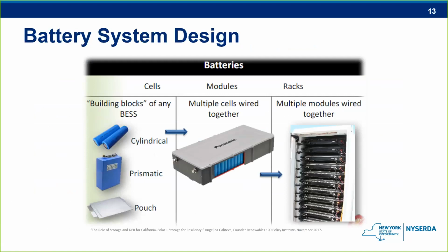All right, so every energy storage system is usually going to consist of at least these three components. The first, over on the left-hand side, is the cell that's considered the building block of the system. They tend to be smaller. They might range in size from something akin to a AA battery or what's in your cell phone to perhaps maybe even the size of a small tablet. Next component is the module, which just really consists of multiple cells that are wired together. And then when multiple modules are wired together, that creates what we refer to as a battery rack.